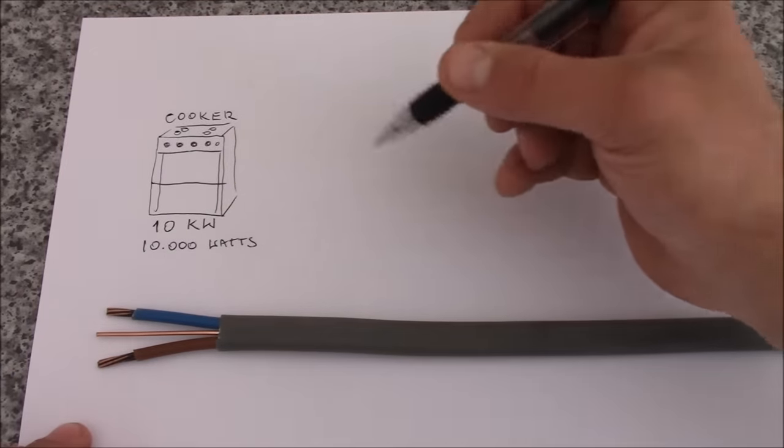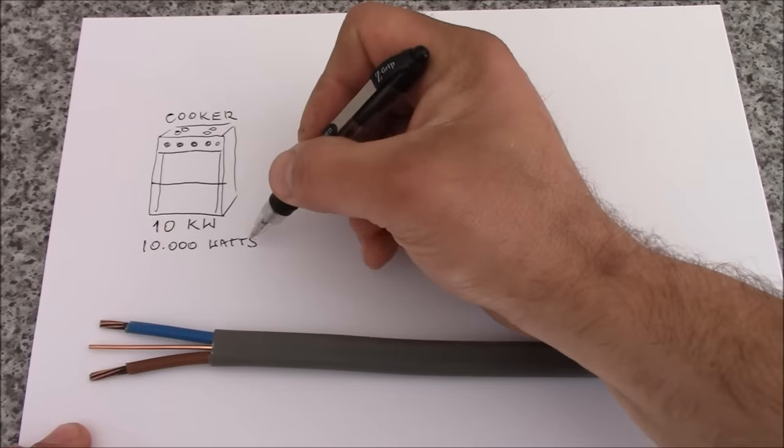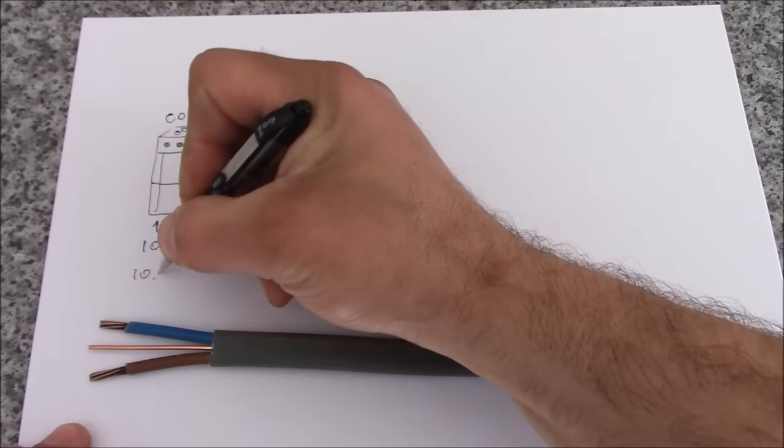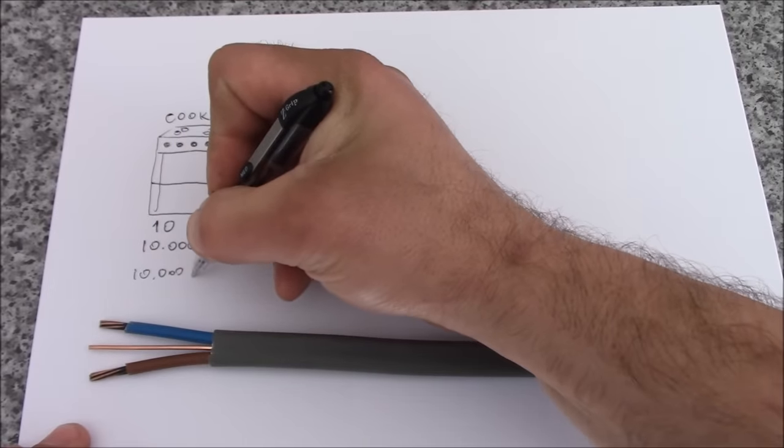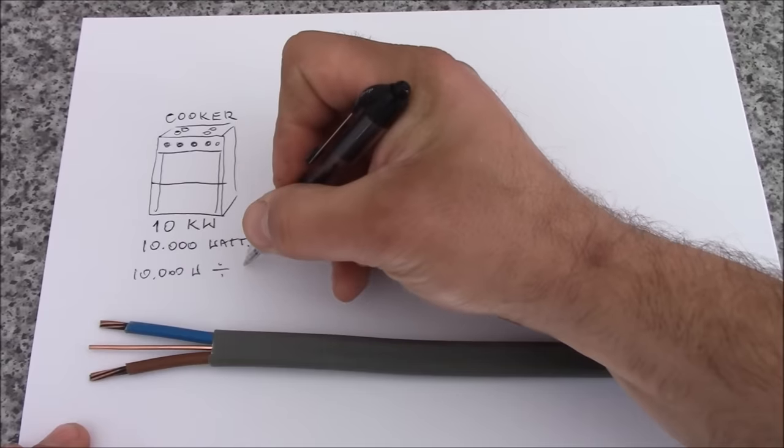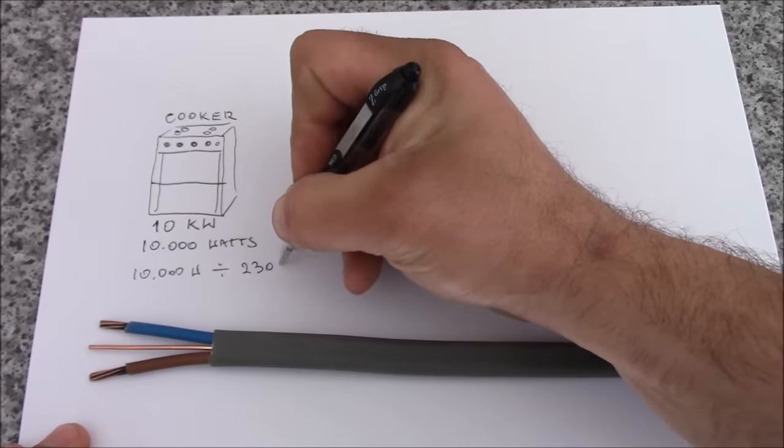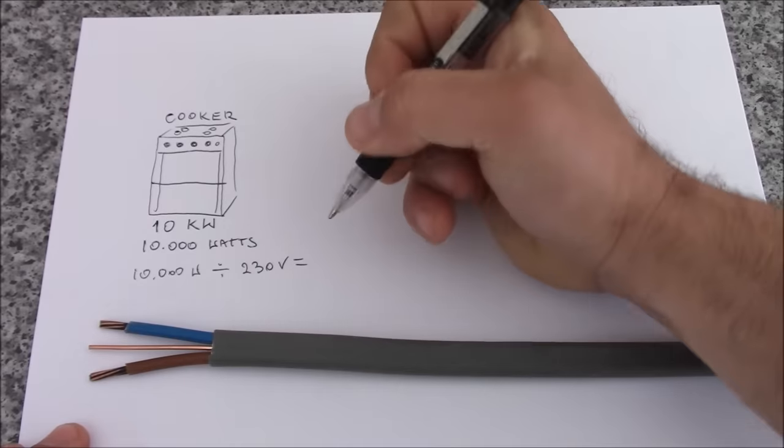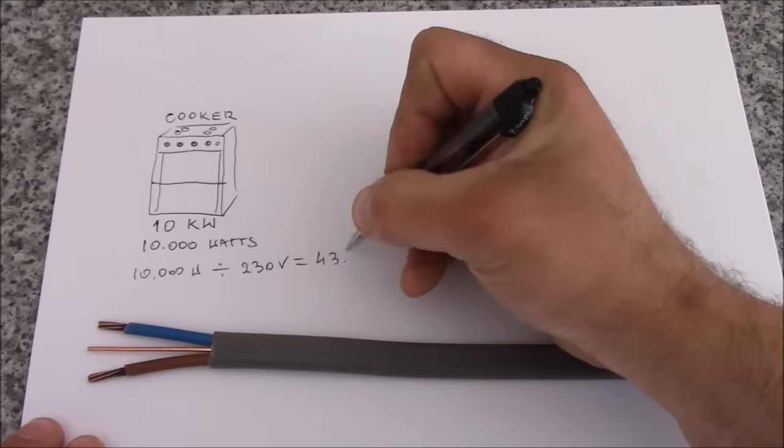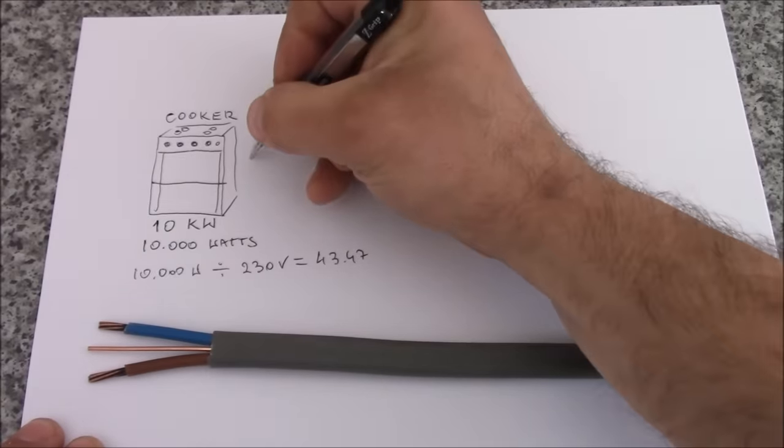Now to calculate the cable size we need amps not watts. So we need to convert the watts into amps. So basically 10,000 watts you have to divide by the voltage which is in UK 230 volts. And this gives us something about 43.47. So let's say 44 amps, that's our cooker.